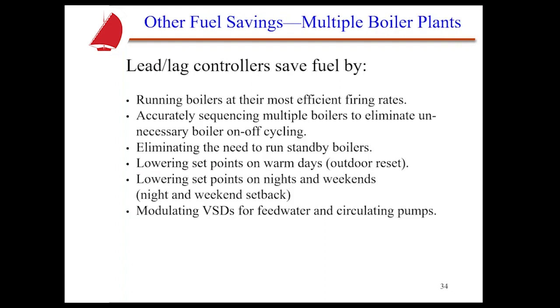Now, one of the things we didn't talk about, but is built into some systems, is lead lag control. Obviously, you want boilers running at their most efficient firing rate, but you want to sequence boilers, if you have multiples, on and off in a manner where it makes the most sense from an efficiency standpoint. So you want to eliminate the need to run those standby boilers if they're just sitting there and they're not needed. Obviously, the correct lead lag control can do that. You can also lower set points from external type control, which would be outdoor reset. We could also lower set points for nights, weekends, or whatever. So this could be controlled by an external device.